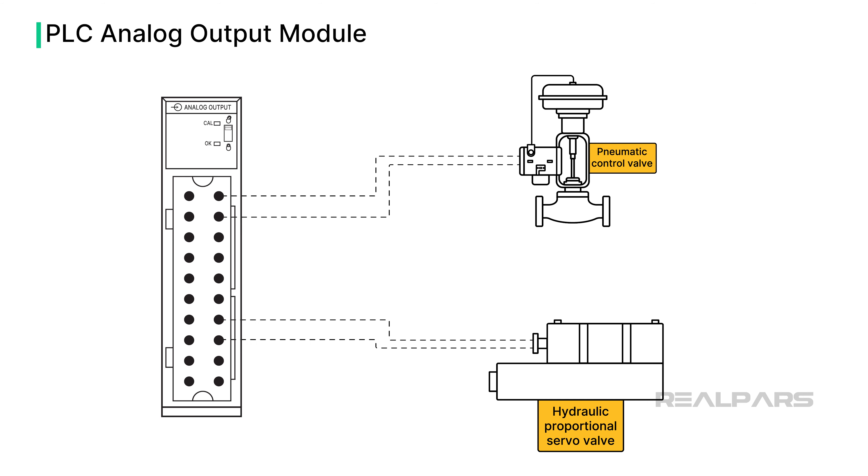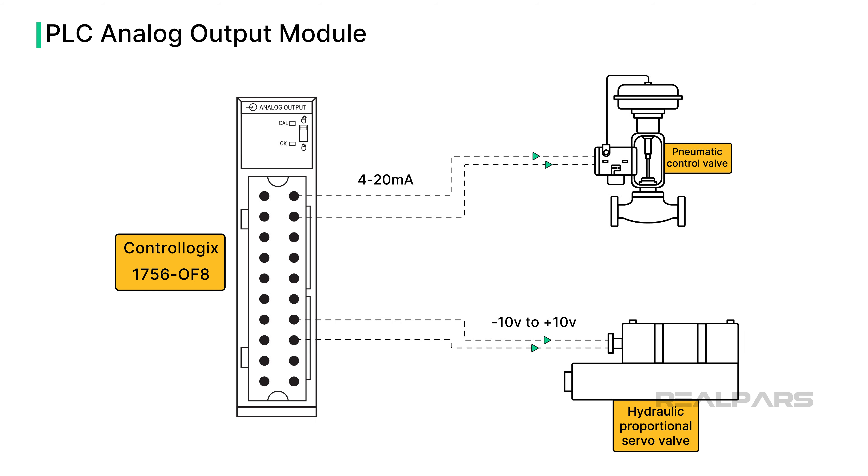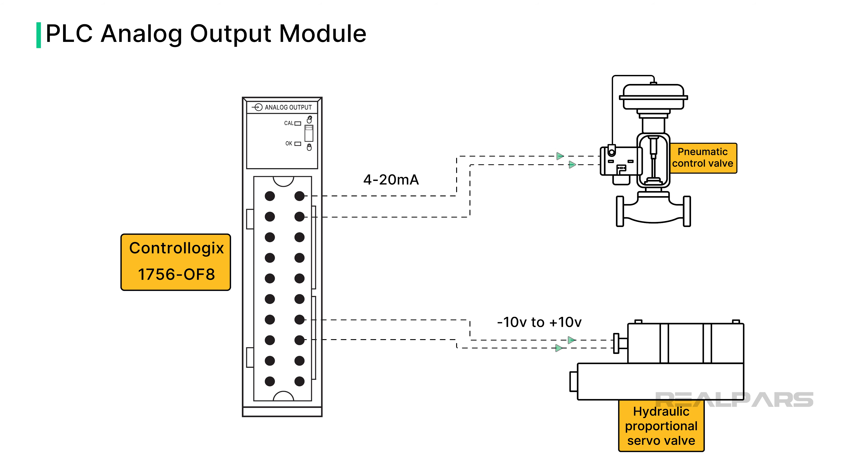Just like on the input side of the PLC, typical output voltage signals include 1 to 5 volts, 0 to 10 volts, and negative 10 to positive 10 volts. The most commonly used analog output signal is a 4 to 20 milliamp current. An example of a typical analog output module is the Allen-Bradley ControlLogix 1756-OF8, which can control eight separate voltage or current devices.